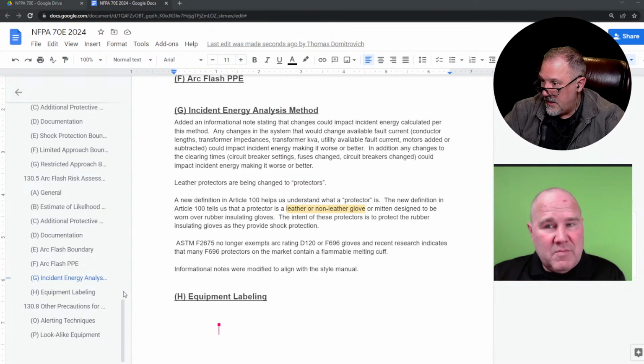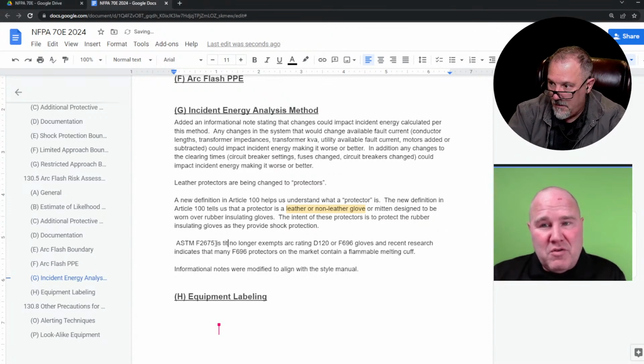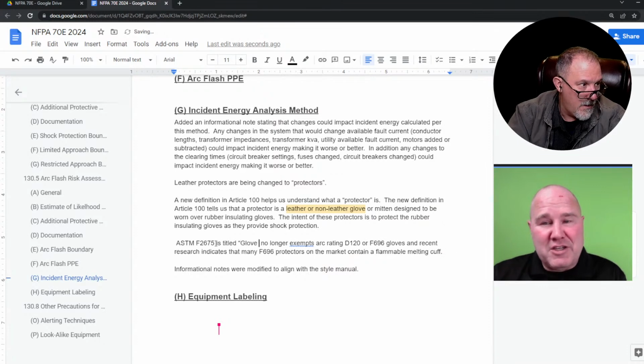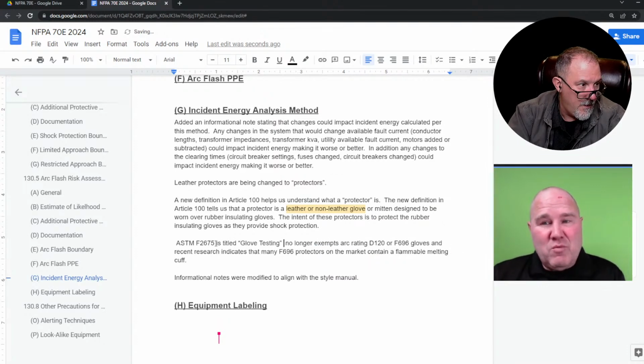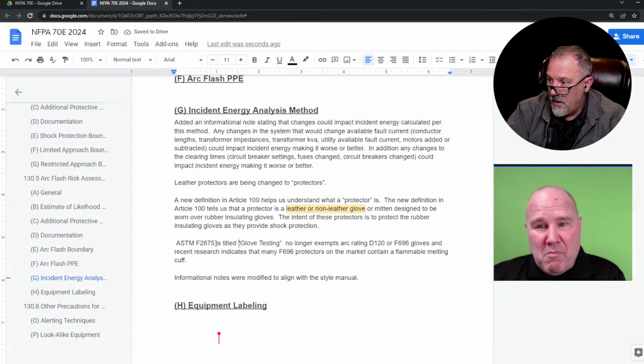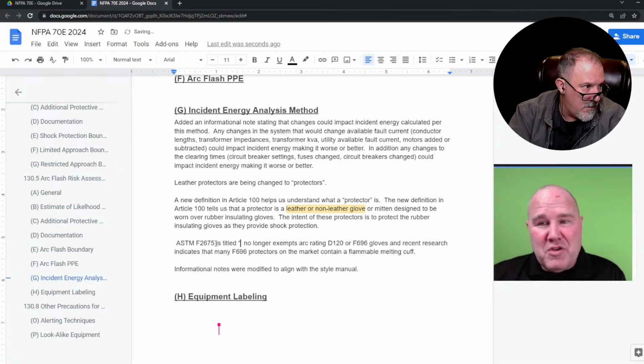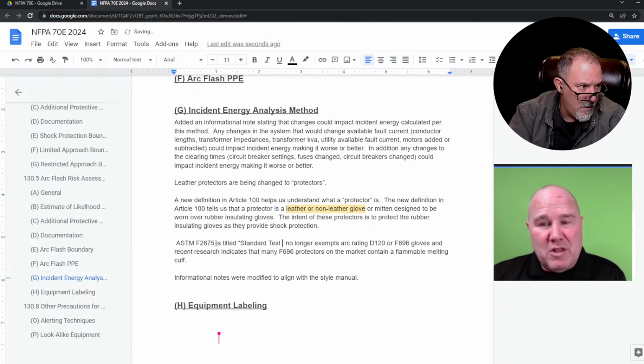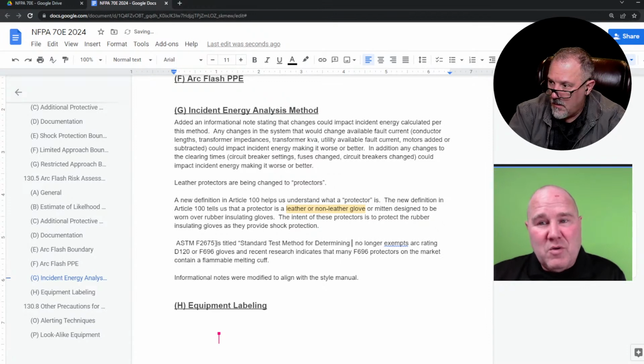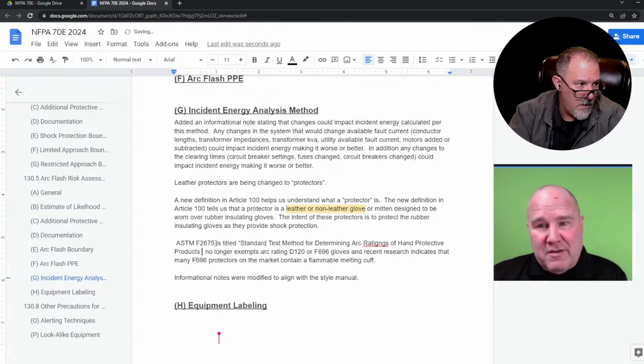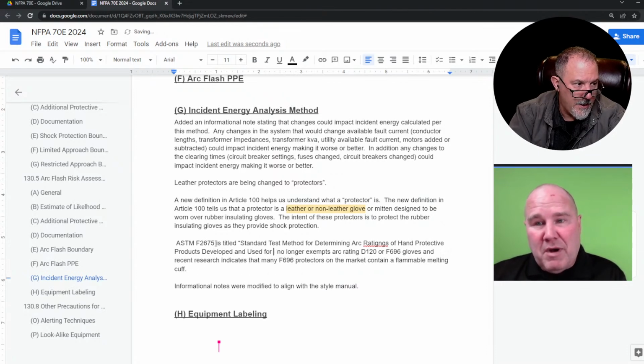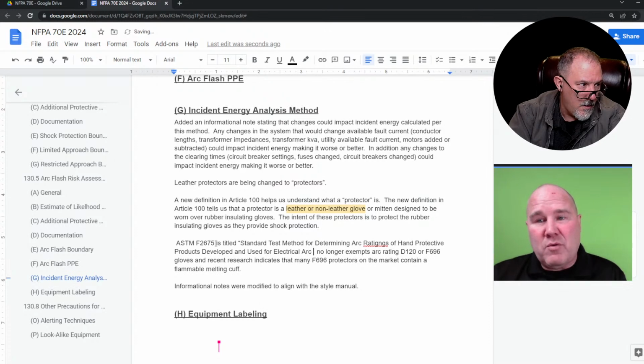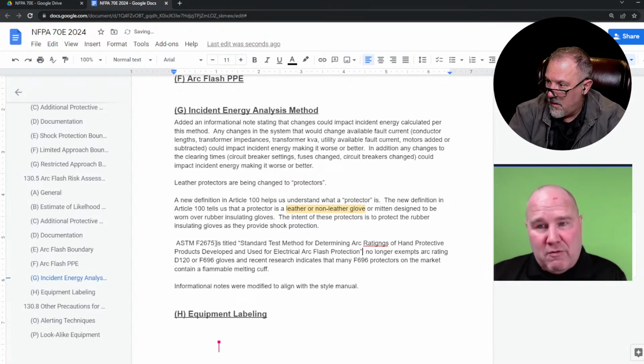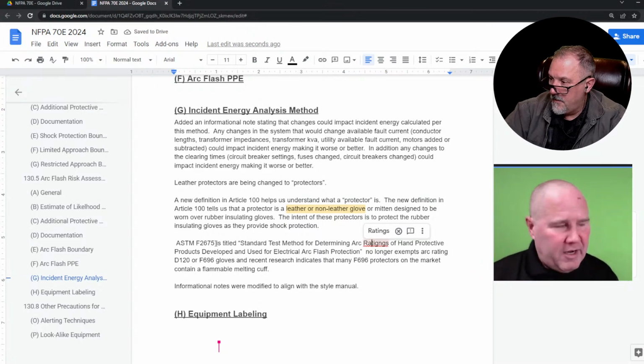All right. Did you know that NFPA 70E allows the use of a voltage rated glove as protection from electrical shock without the protector on it? Wait, say that again? That you're allowed to use a rubber glove to protect yourself from a shock hazard without the leather protector? It's specifically stated in 70E, but you can only use it once, and you have to send it in for testing after you've used it. Oh, I don't know. If you look at the arc flash PPE part of it, you have to wear the protector with it for arc flash. But I don't know that. I'm going to grab my gloves. Hang on. Yeah.